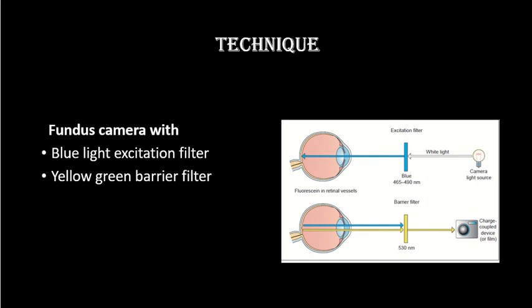For the technique of fundus fluorescent angiography, we use a camera with a white light source. This is split by an excitation filter which allows only blue light of 490 nm to go into the eye. When the light comes back, a barrier filter blocks the blue light and allows only light of longer wavelength — yellow light of about 530 nm — to reach the camera to make the image. So there are two built-in filters in this fundus camera.